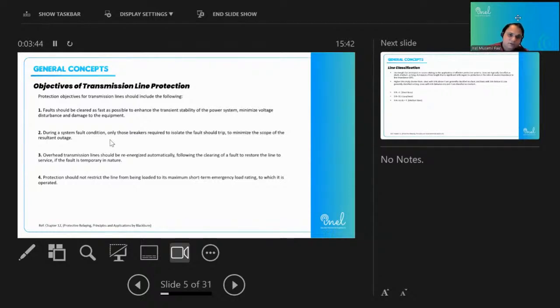the protection system should not be so sensitive that it will operate when the transmission line is operating near or at its thermal stability limits. So it should know which magnitude of current is a fault and which magnitude is an overloading or heavily loaded condition of the transmission line. So these are the basic objectives of transmission line protection which we need to consider. When we discuss the protection calculations and the implementation, I'll explain it a bit more.